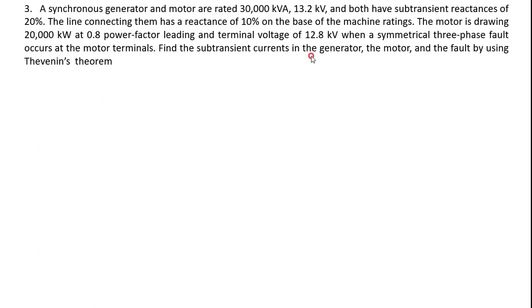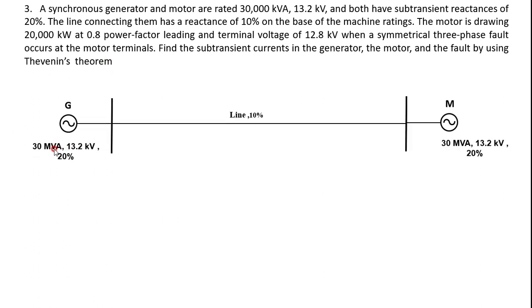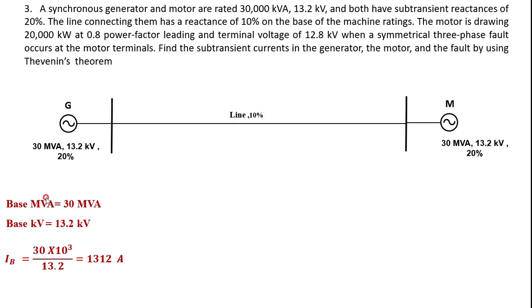We need to find the subtransient current contributed from the generator, motor, and the total fault current. For this numerical, this is a single line diagram — both machines are 30 MVA, 13.2 kV with 20% reactance, and the line has 10% reactance. The base quantity is taken as 30 MVA, 13.2 kV throughout the circuit, since there is no transformation between sections.